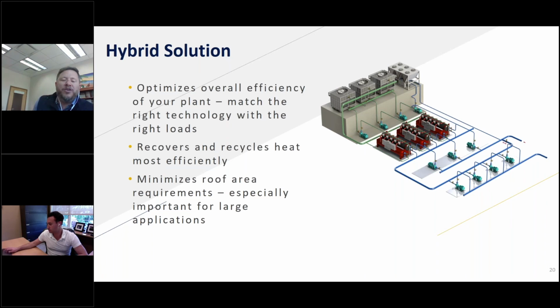And as I said, you minimize the amount of roof space if we start to pull some of that load off of an air source heat pump plant with a water-cooled chiller or a heat recovery machine that can go inside the building. So it really is about how we start thinking holistically, big picture, about what's the best way, especially with the advent of more and more efficient heat recovery chillers. Now we have a machine that can really provide dual purpose. It can make really efficient chilled water and hot water at the same time.